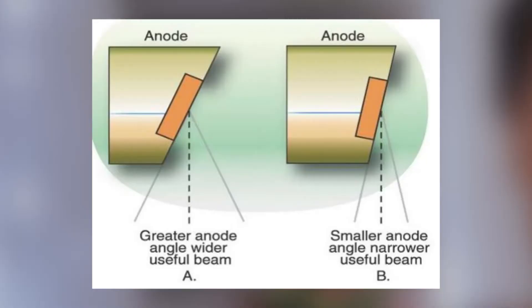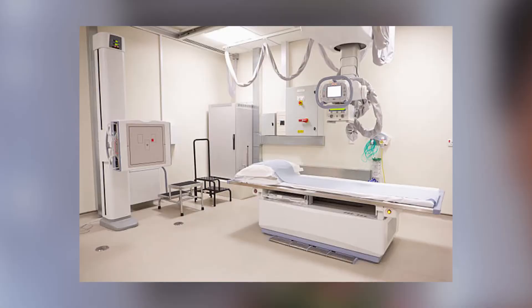The anode is positively charged while the cathode is negatively charged, since electrons travel from the cathode side. The anode target is usually angled between 5 to 15 degrees. In order for x-rays to be produced, we need energy, which comes from the generator. The generator is connected to the x-ray tube through an electrical circuit and converts AC — alternating current — into direct current, so that negatively charged electrons flow correctly toward the positively charged anode and not in mixed directions.